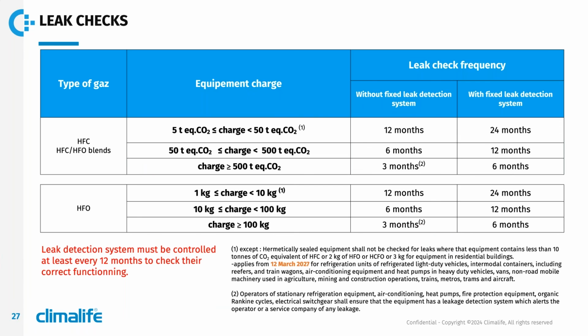What about leak detection? The F-Gas 2024 regulation covers two families of refrigerants: the family of HFCs and HFC-HFO blends, and the family of pure HFOs. For the HFC family, we find exactly what we had in the F-Gas 2014. Leak checks must be done depending on the charge of the installation in tons of CO2 equivalent. Between 5 and 50 tons of CO2 equivalent, you have to control the leaks every 12 months, or every 24 months if you have a fixed leak detection system installed.